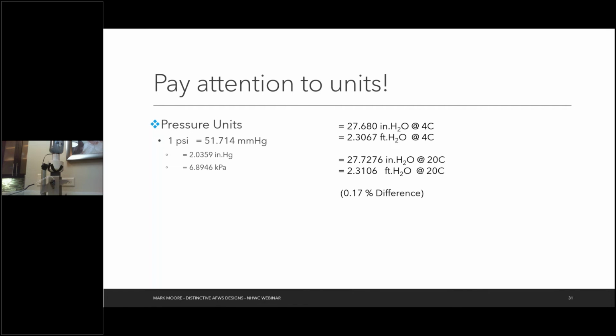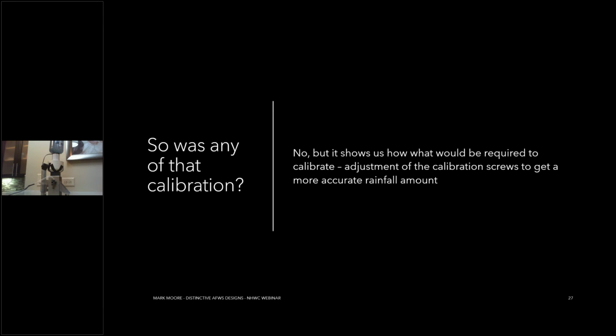Hey, Mark. Go ahead. We have a couple questions about the tipping bucket calibration. Joshua Krennick asks, assuming your nylon stopper does not move, how does a tipping bucket fall out of calibration? Yeah, so tipping buckets can fall out of calibration by a few different methods. Typically, it will be things like if it's very dirty, which is why you would clean a tipping bucket before calibration. Those bearings just start to age, so as the tipping bucket ages out, they'll start to be not as smooth, and this dynamic calibration will show that it's not as accurate as it used to be. The other thing is those nylon stoppers should stay still, but as we talked about, sometimes these are on bridges which are vibrating and bouncing, and so that can have an impact there. But usually it's more the tipping mechanism itself that's causing it to go out of calibration if those nylon stoppers aren't moving.